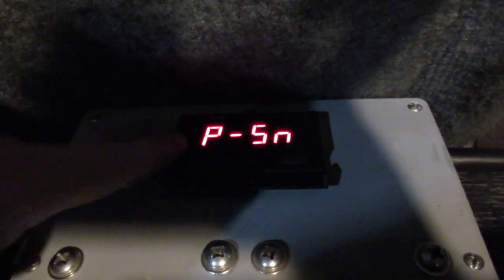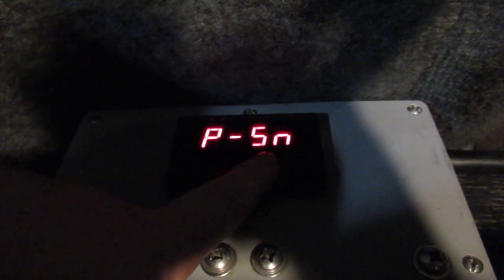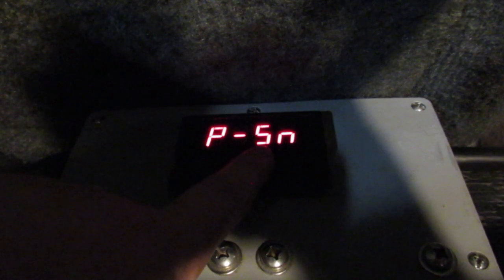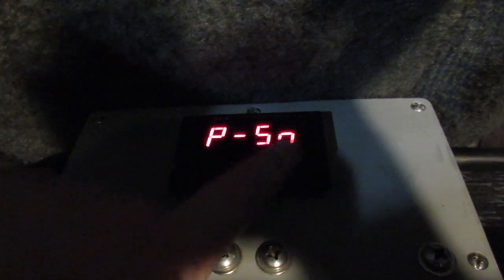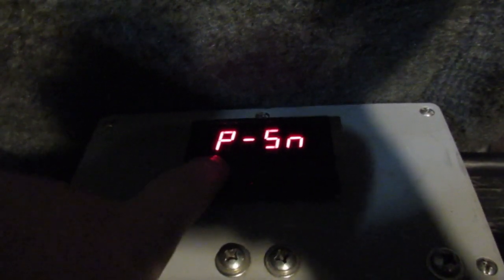This is the P-SN setting. It's the only one in the list ending in that, and what that means is this is the voltage sense leads - which screws do you want your reading from? Is it the 10 volt, the 100 volt, the 500 volt? Whatever, you have to pick here. There's a nice little chart that Jack put together that shows it. But 0 happens to be the one that is for 500 volts. So anything above 100 volts and lower than 500 volts, which is my pack, has to be that.